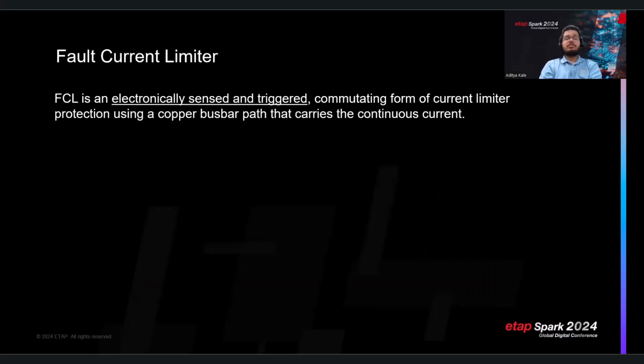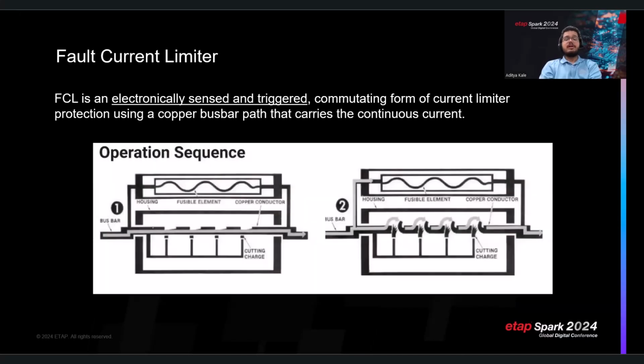How does the FCL operate? Let's break it down. Under normal conditions, the copper bus bar safely carries the load current. In the event of a fault, explosive charges located under the bus bar are triggered by the firing logic. This causes the bus bar to be physically severed. As the conductor is being cut, arcs form in the resulting gaps. The short circuit is thus diverted to the fusible element, which rapidly melts and clears the fault. The entire process occurs within a quarter of a cycle, meaning the fault is cleared before the first peak of the fault current, drastically limiting the damage.